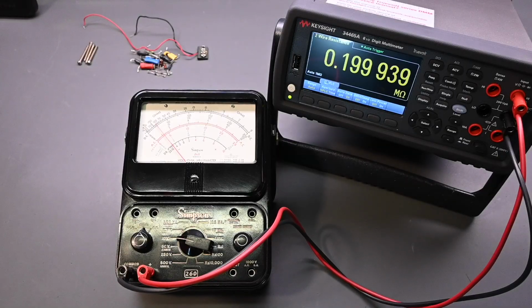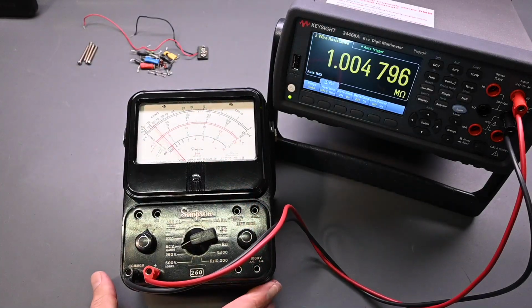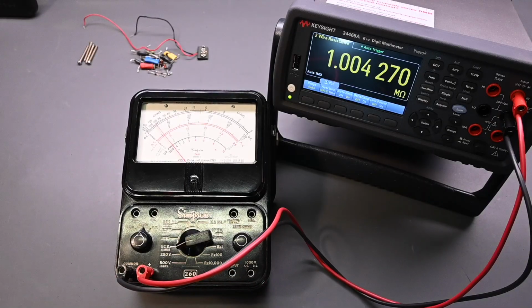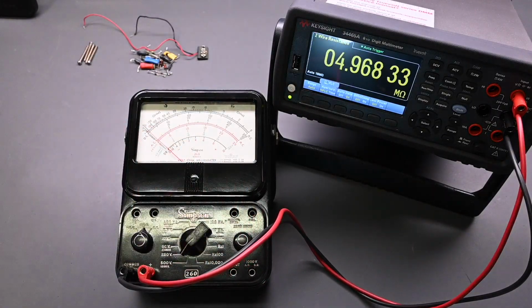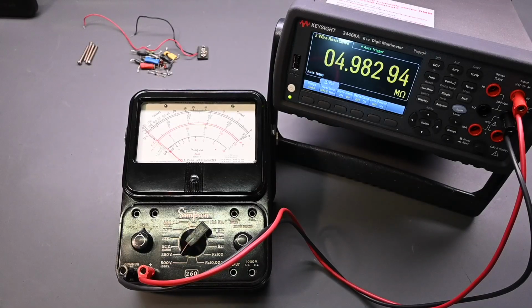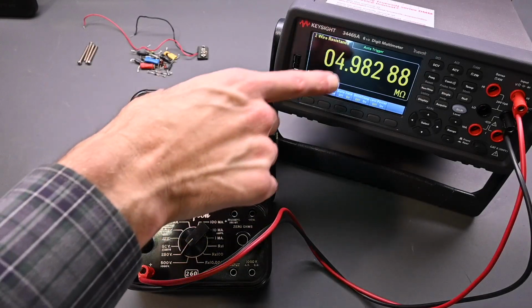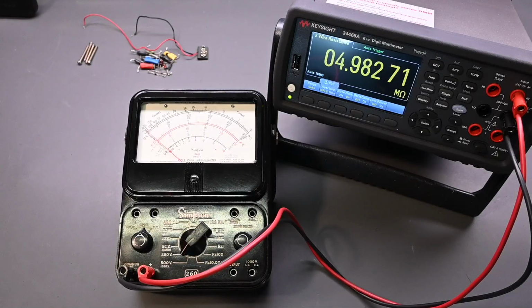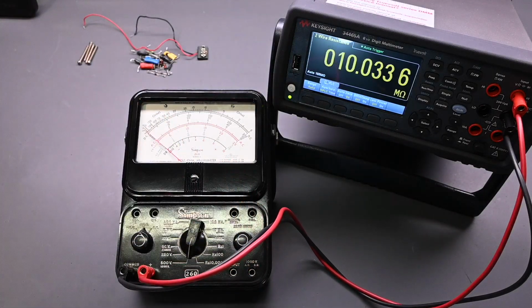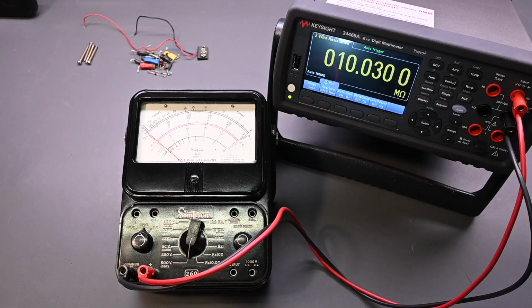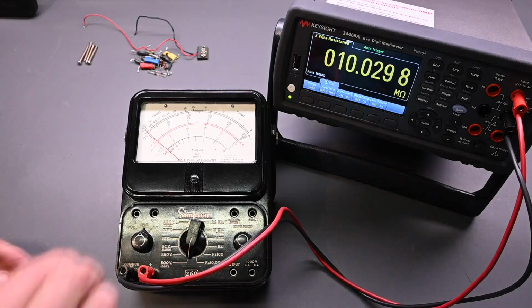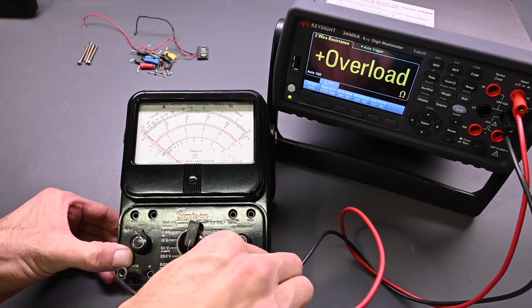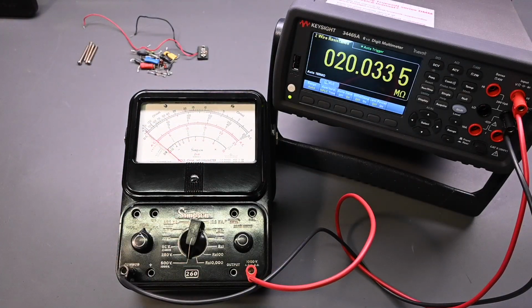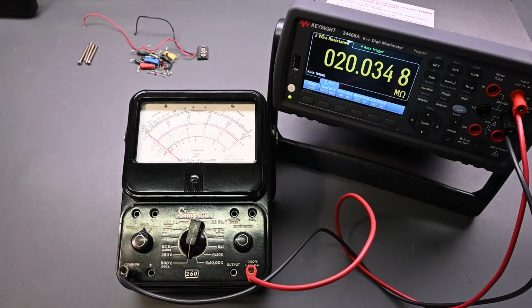200K, so this is in the meg ohm range now, so perfect. No problems there. So 1 meg ohm, excellent, that's what that should be. 250 volts. So that should be 5 meg ohms, very close to that value, just a touch under, but that shouldn't be any problem. Looks very good. And the 500 volt range, 10 meg ohms, perfect. That looks great. And then 1,000 volts, we just have to move this over right here. And it should be 20 meg ohms, perfect, it is. Excellent. So the resistance readings look great. I think the accuracy is going to be very good on the meter.